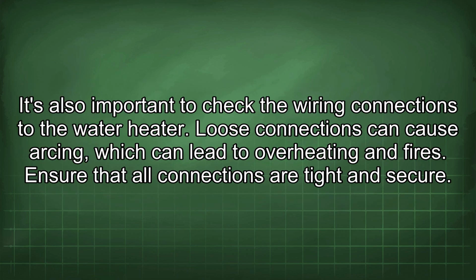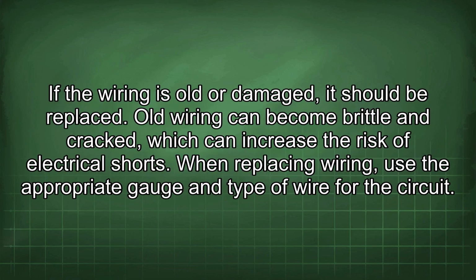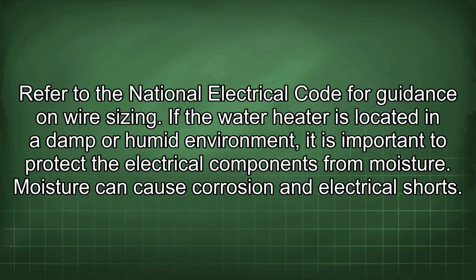It's also important to check the wiring connections to the water heater. Loose connections can cause arcing, which can lead to overheating and fires. Ensure that all connections are tight and secure. If the wiring is old or damaged, it should be replaced. Old wiring can become brittle and cracked, which can increase the risk of electrical shorts. When replacing wiring, use the appropriate gauge and type of wire for this circuit. Refer to the National Electrical Code for guidance on wire sizing.